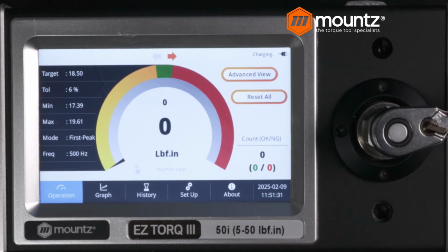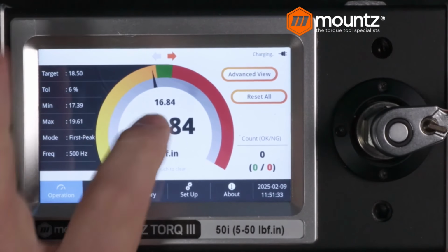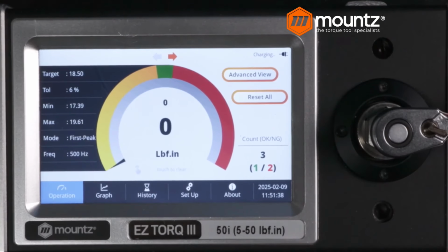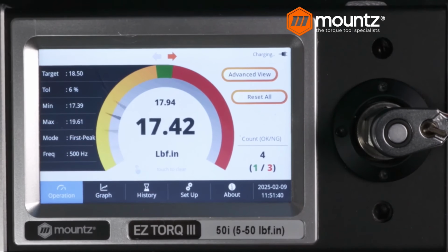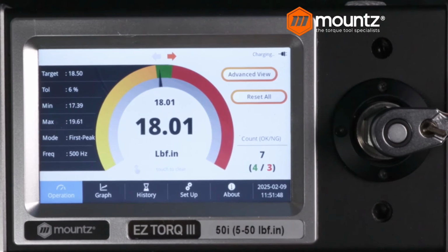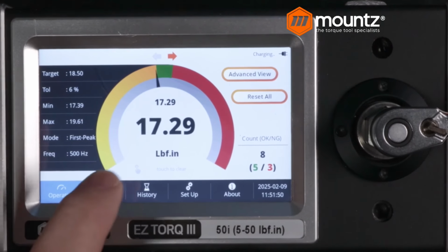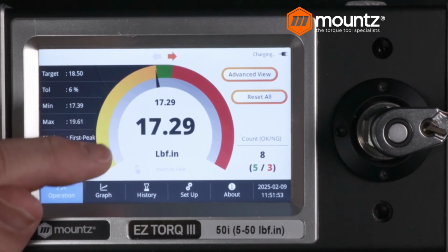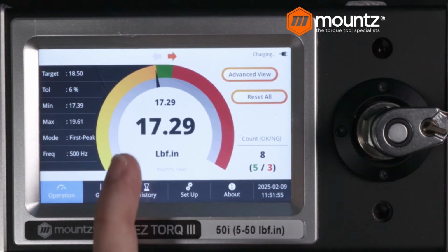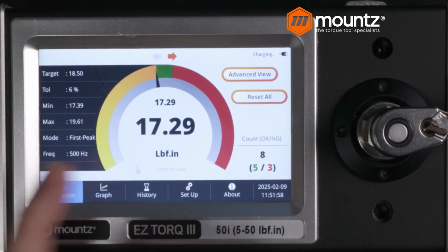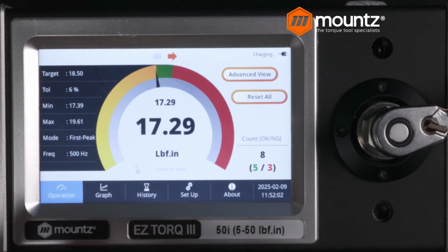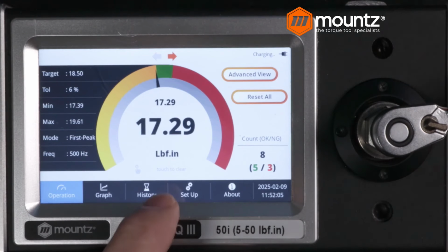Now, if I pull the wrench correctly and get the click, that was not correct. There we go. So I have it set to 18.5 inch-pounds, and we're getting around 17.5 or so. Now, what you'll see here is that we have two different values on the screen. So the larger value is going to be where the wrench clicks, and then the second number is going to be where the wrench actually stops.